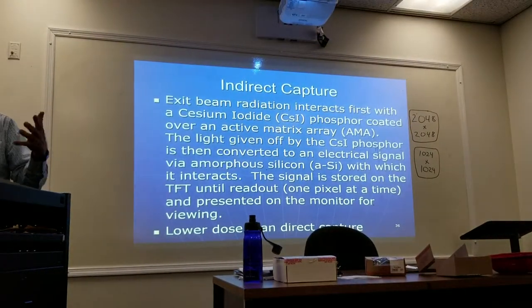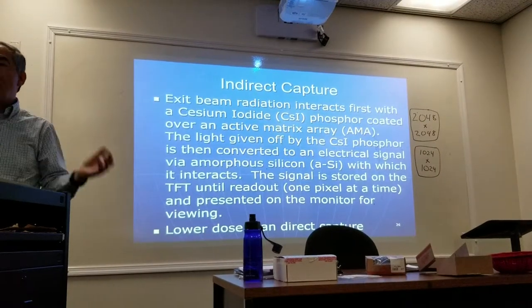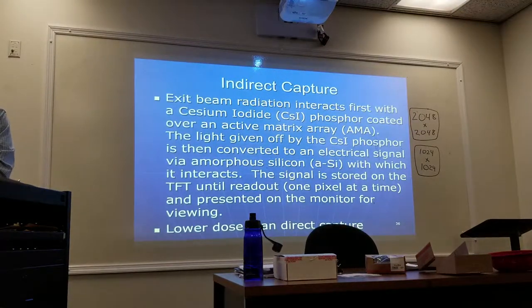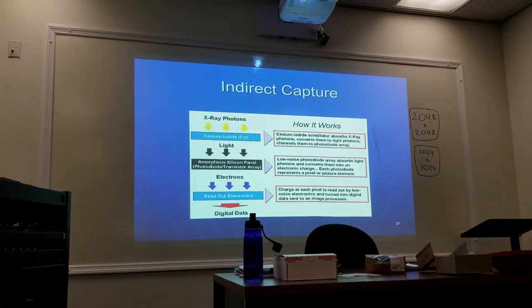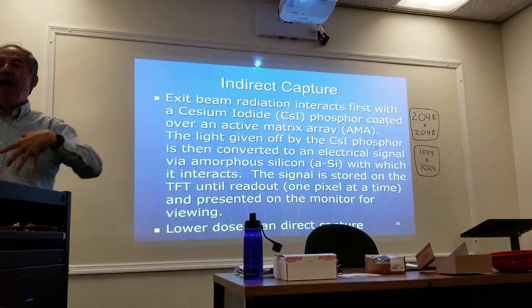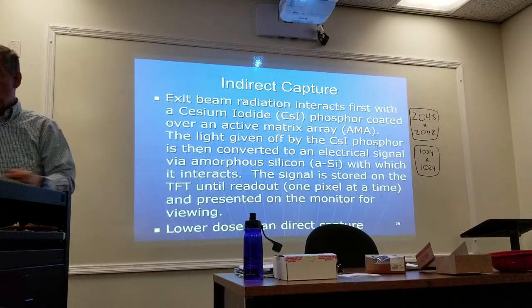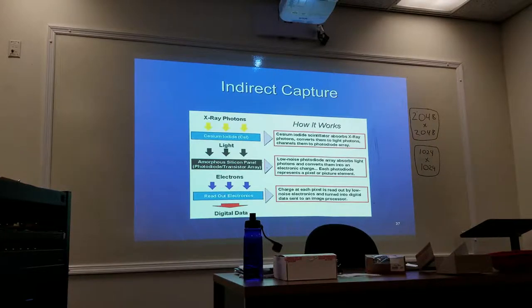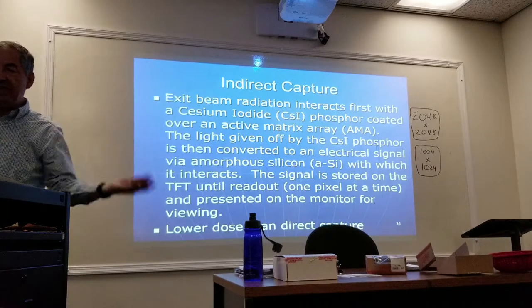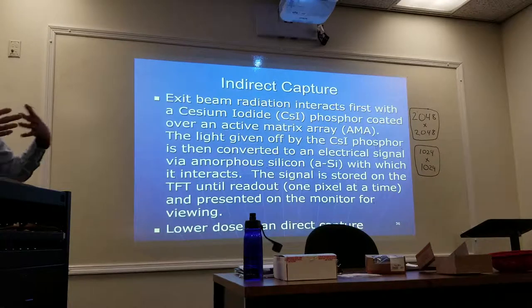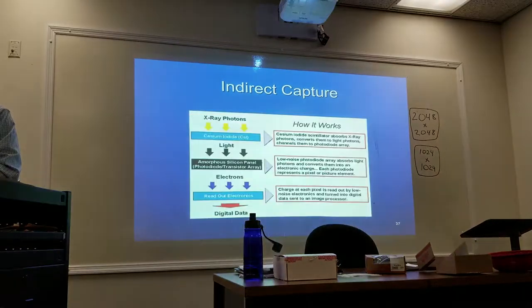With direct capture, the x-ray that goes through the patient is converted directly into an electrical signal — it skips the light stage. For indirect capture: the exit beam radiation first interacts with cesium iodide phosphor coated over a matrix. The x-ray photons strike the cesium iodide, which gives off light, and that light is converted to an electrical signal using amorphous silicon.